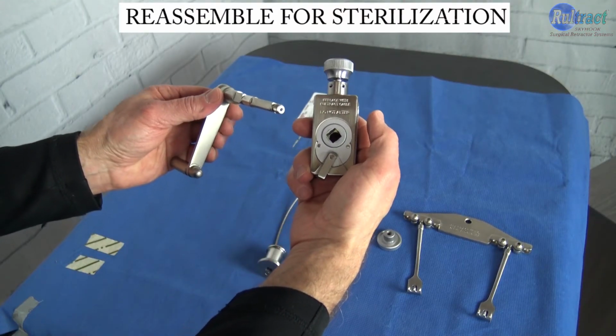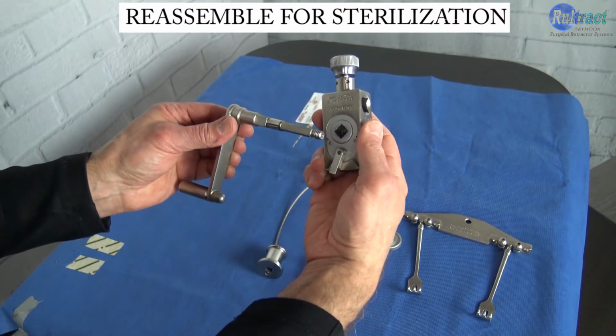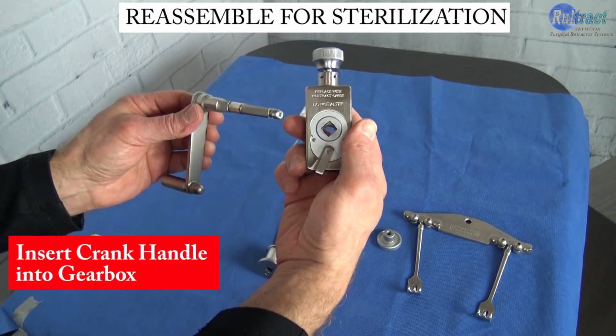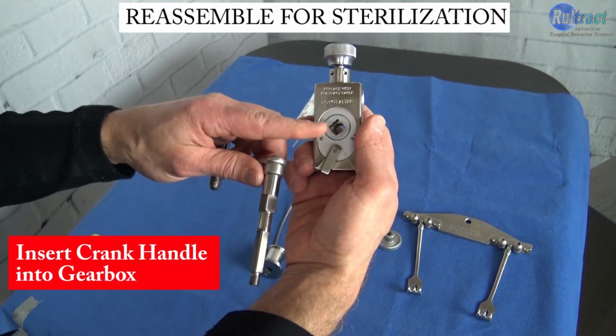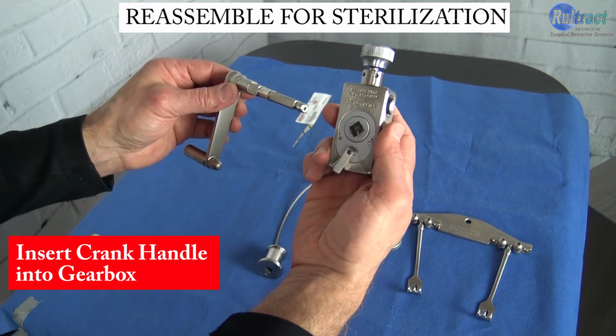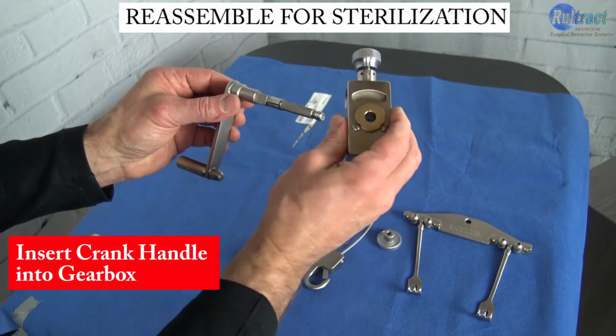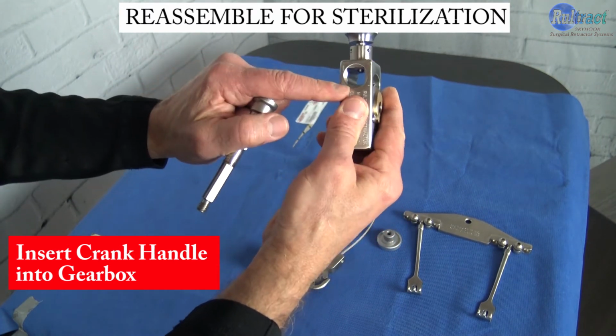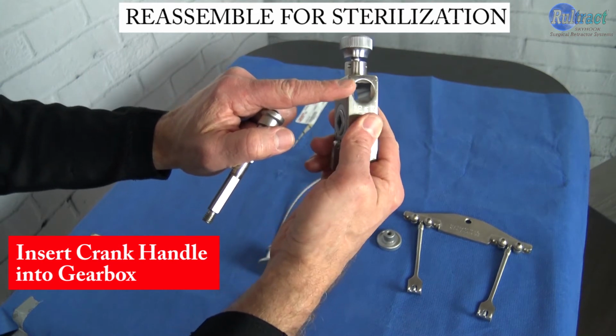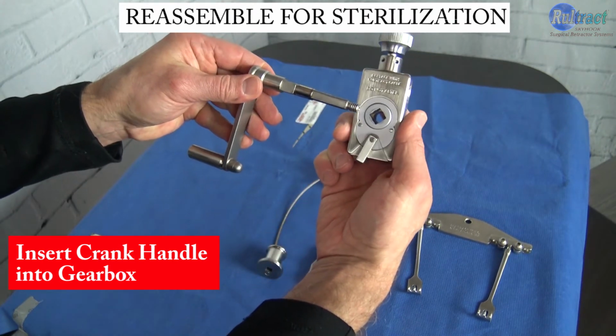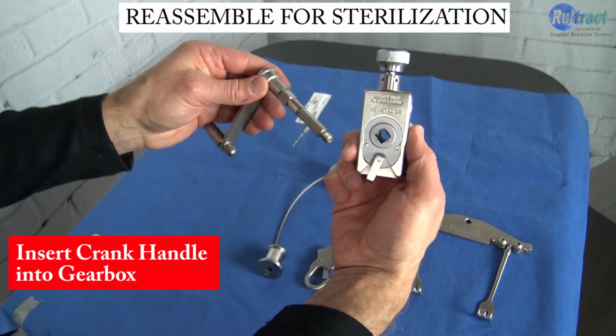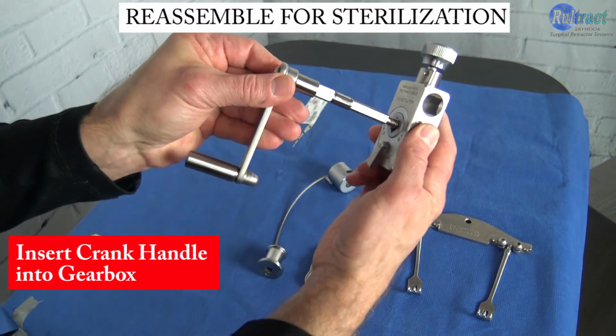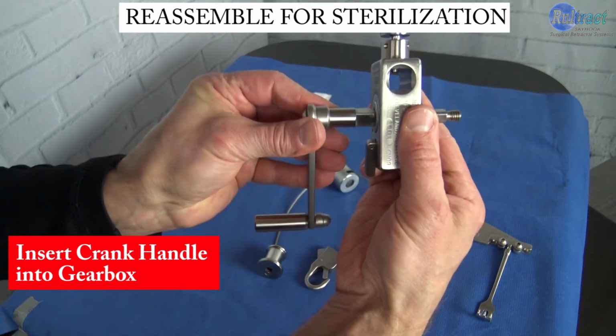First, we're going to insert the crank handle into the gearbox. Now, you remember when we disassembled this, we removed the crank handle from the square hole. So we want to be sure that we're putting it back into the square hole and not the round hole. Now, there is a square hole here, but that's not the right hole to put this in. Go ahead and put it into the square hole right above the ratchet reversing lever. Make sure that it sits flush.